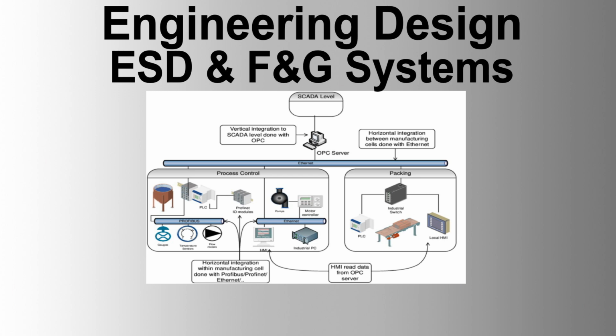The software within the DCS controllers, ESD F&G CPUs, and operator stations shall be fully tested for compliance with the functional requirements defined within the specification and other purchaser's documents furnished in this RFQ. RF interference test. This test shall be conducted by operating a portable radio of frequency and power defined by the purchaser at a distance of 1 meter from each item of the equipment with doors fully open. The system shall be monitored for abnormal indications or spurious data.